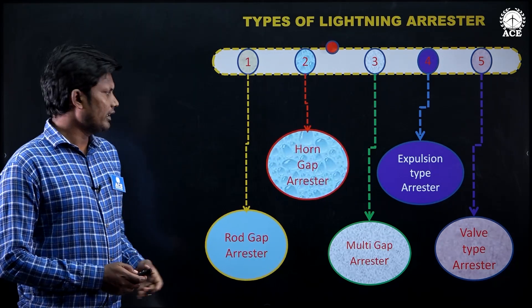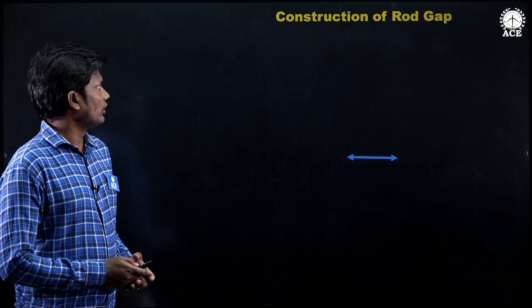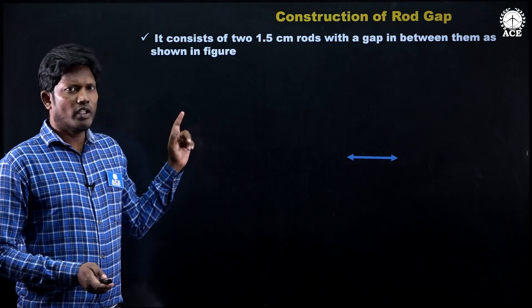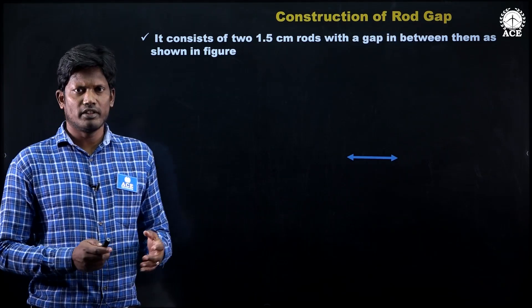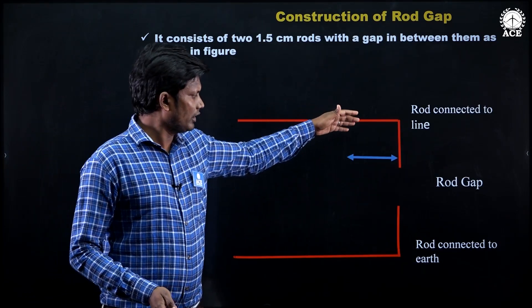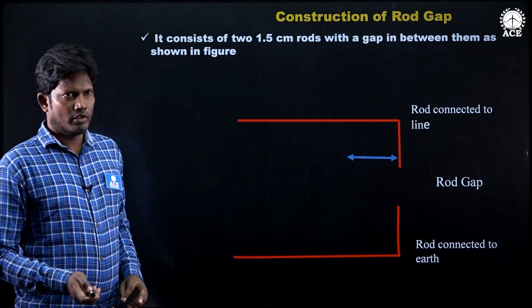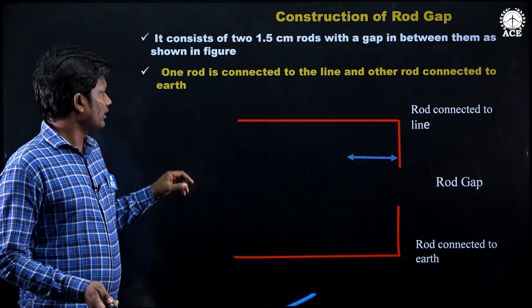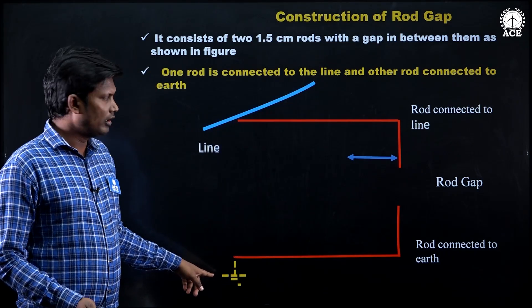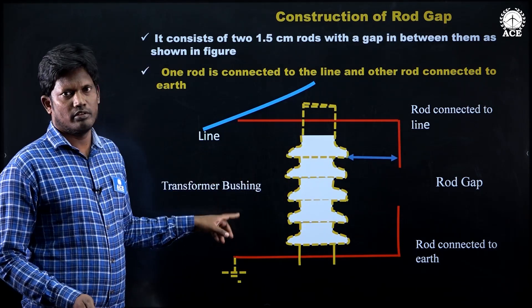The first one is rod gap arrestor and the second one is horn gap arrestor. Now the construction of rod gap arrestor: it consists of two 1.5 centimeter rods with a gap between them as shown in the figure. This is rod 1 and this is rod 2, and between them the gap is there. One rod is connected to the line and the other rod is effectively grounded in order to protect the insulators which are placed on the transformer bushing.